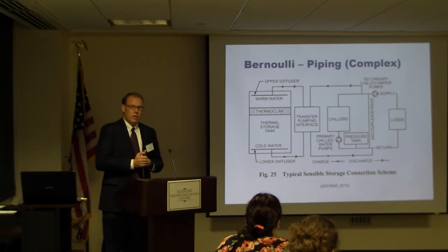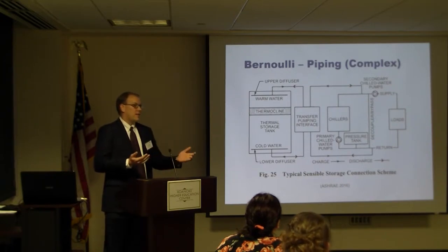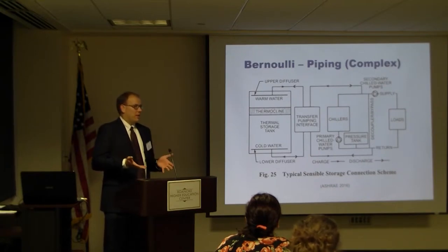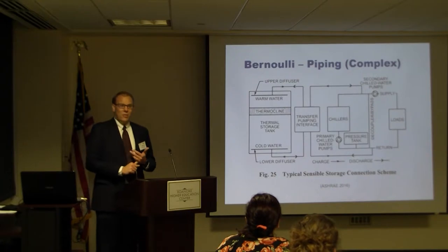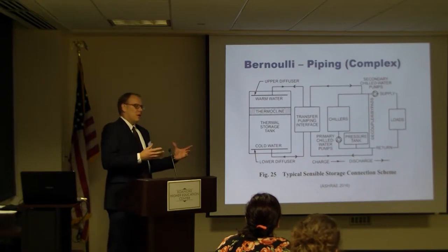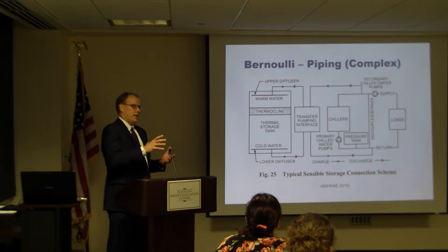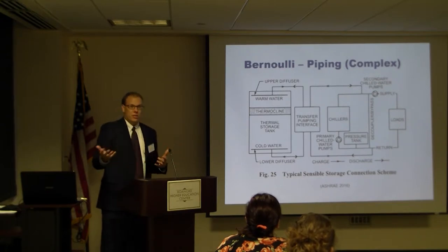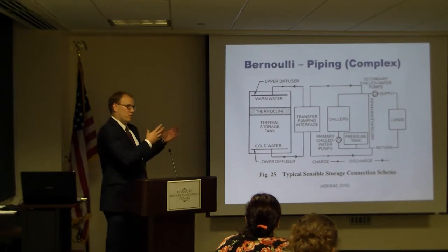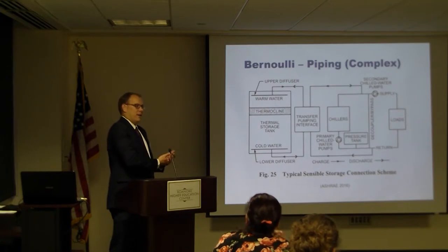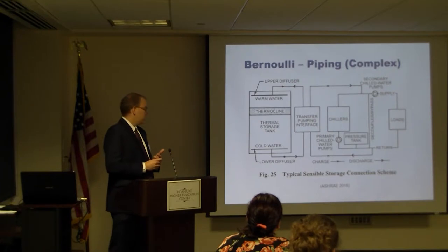One of the things we start to do is play with electricity rates. In Texas and in the Midwest states, a lot of wind energy and free energy is generated at night, very low cost energy, so they have excess energy because at nighttime we're pretty low on energy demand. Our peak energy demands tend to be middle of the day when everybody wants full air conditioning. So how do we take advantage of that situation? One of the scenarios we use is called thermal energy storage, whether it's a chilled water storage tank where we generate a whole bunch of cold water at night, we store it at about 40 degrees, and during the daytime when energy cost is expensive and we don't want to make chilled water, we'll drain that tank down. So you'll warm that tank up during the day, cool it back down at night, and then transfer that energy out during the day.